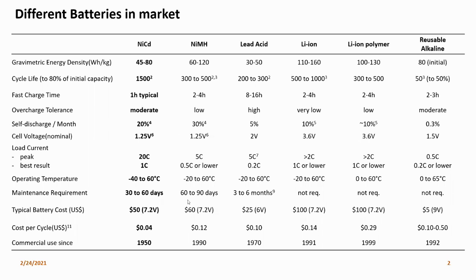If you see, there are a few things like cell voltage, which is 1.2 volts, and it has one disadvantage compared to lead acid, which is the self discharge of the battery. It's 20% per month, so that is a major disadvantage for a system if it's idle. But in most cases, if you use it as a storage system, hopefully it will not be an issue for day-to-day cycles.